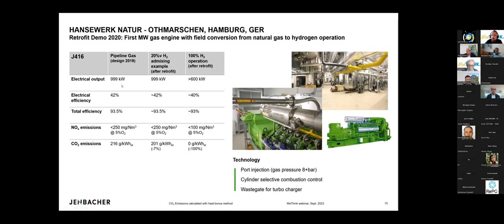There's some performance data on the left-hand side. Running on pipeline gas, this engine was optimized for total efficiency over 93%. We did some blending of hydrogen at 20%, which could typically happen in pipeline gas, and total efficiency and output didn't change. Running on 100% hydrogen, since the engine is designed for natural gas, power was reduced to about 600 kilowatts, but total efficiency still didn't really change. Very interesting were the NOx emissions, which dropped from 250 milligrams to less than 100 milligrams, another advantage of running on hydrogen.